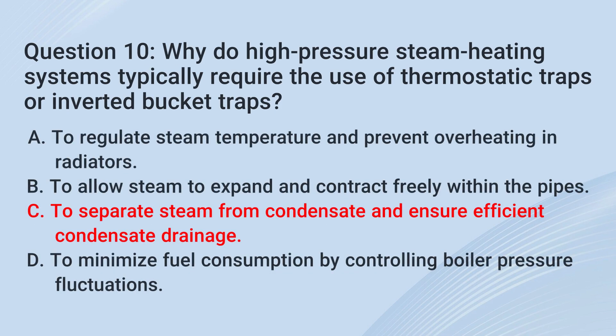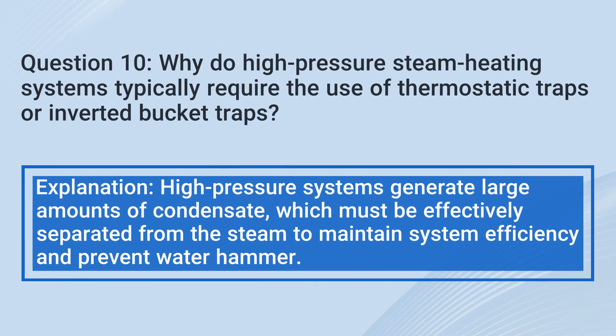The correct answer is C. To separate steam from condensate and ensure efficient condensate drainage. High-pressure systems generate large amounts of condensate, which must be effectively separated from the steam to maintain system efficiency and prevent water hammer.